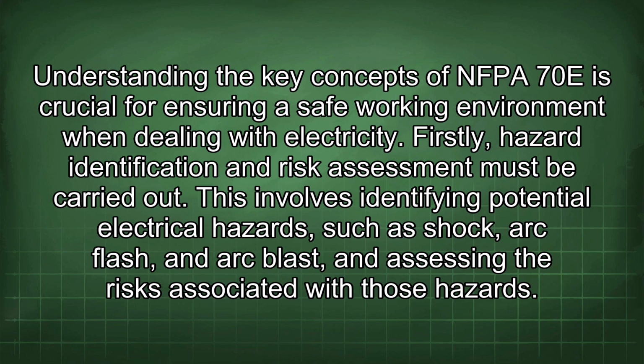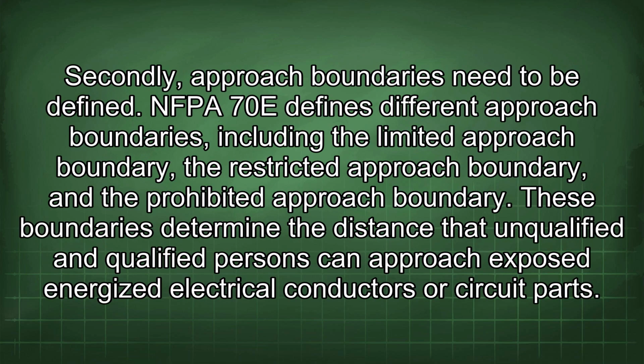Firstly, hazard identification and risk assessment must be carried out. This involves identifying potential electrical hazards such as shock, arc flash, and arc blast, and assessing the risks associated with those hazards. Secondly, approach boundaries need to be defined. NFPA 70E defines different approach boundaries, including the limited approach boundary, the restricted approach boundary, and the prohibited approach boundary. These boundaries determine the distance that unqualified and qualified persons can approach exposed energized electrical conductors or circuit parts.